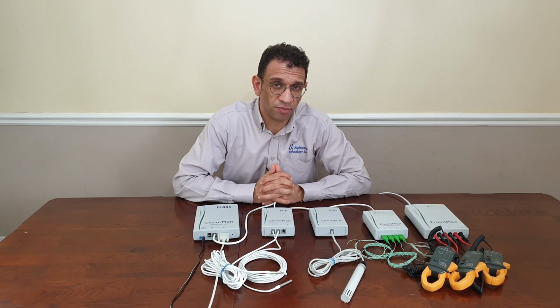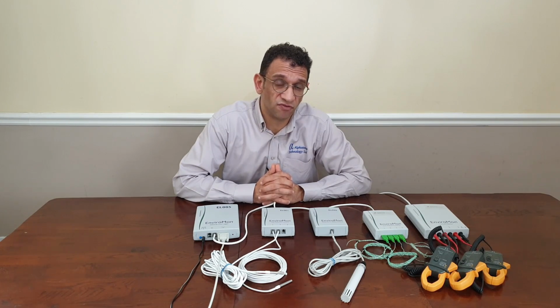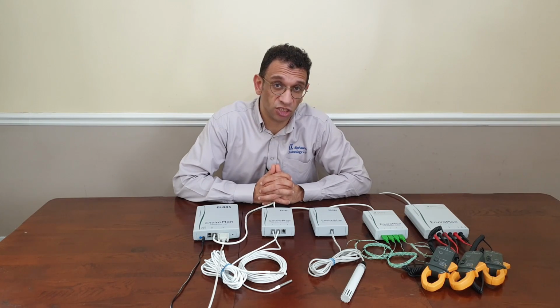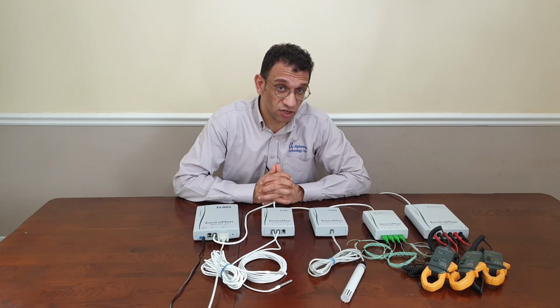The EnviroMon network cable, or as I like to call them, the converter cables, is essential to the EnviroMon system, as it transfers data to and from the converters and logger. It also provides power from the logger to the converters. As such, any issues with the network cable or the converter cable will most likely cause blank readings to a particular converter or multiple converters, depending on where the problem is.